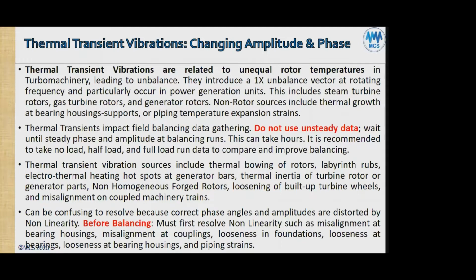And when we're going to do field balancing to reduce such unbalanced vibration, it must be done carefully. You cannot use unsteady data of amplitude and phase. So you typically wait until steady phase and amplitude is reached at the balancing runs, which can take hours. Depending on the size, on a 20 megawatt steam turbine driven generator, the time to stabilize thermally on a new machine in good condition, after a long preheating period, could be 2.5 hours. But if you come to one in not very good condition, worn out and with internal problems, then it could easily be 4 hours. And that's only on a 20 megawatt.